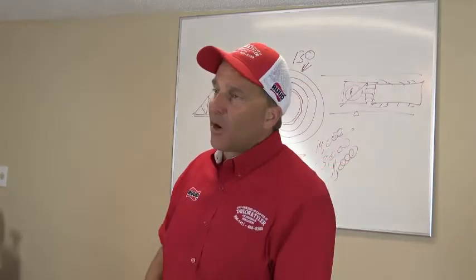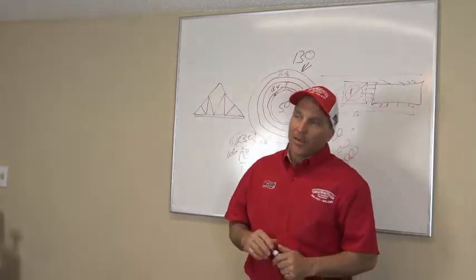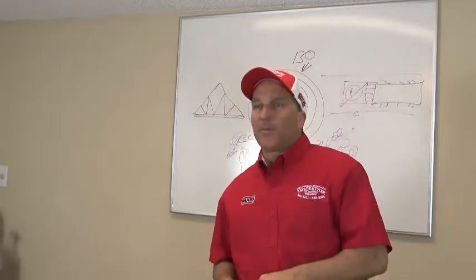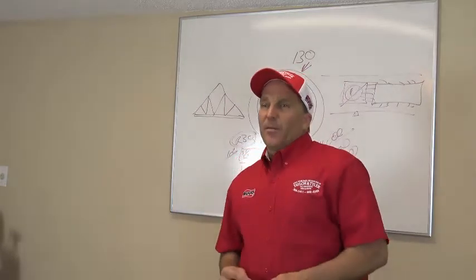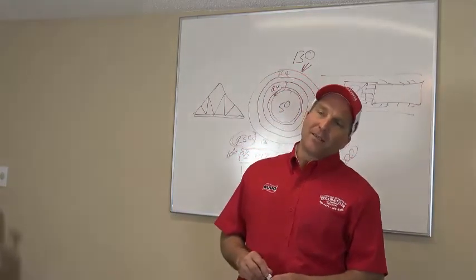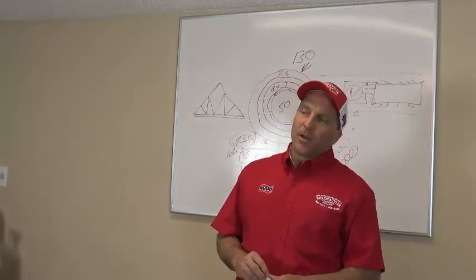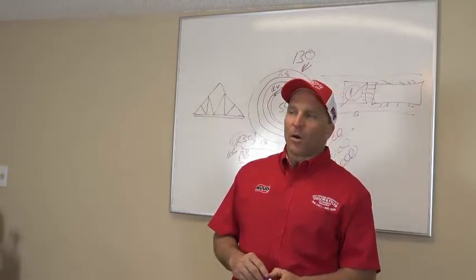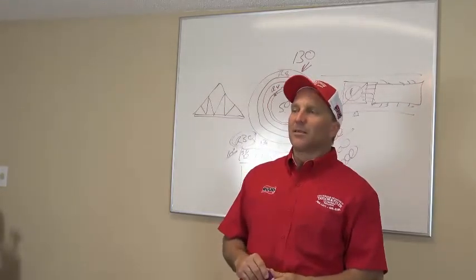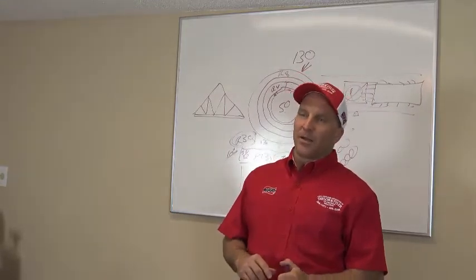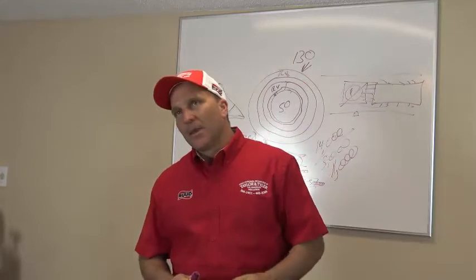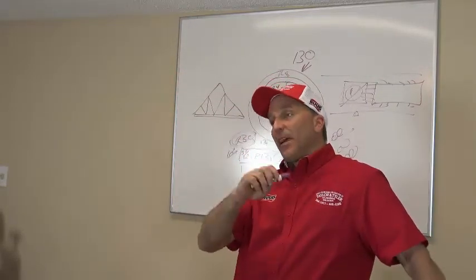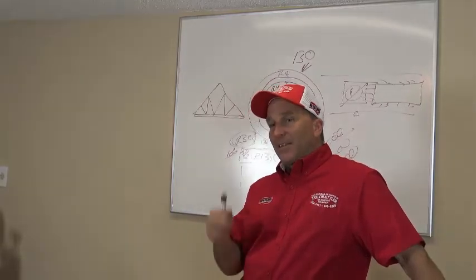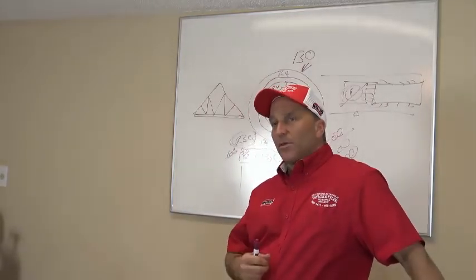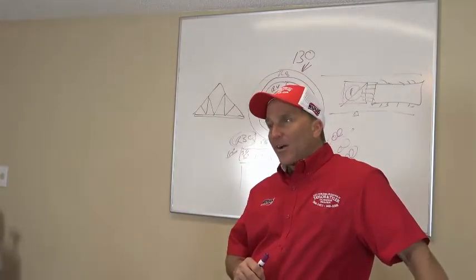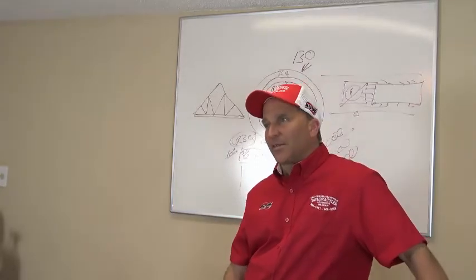I had a guy one time call me up, dude, 9 o'clock at night. This is a true story. 9 o'clock, 9:30 at night, called me up. I was working on one of my rental properties, and he says, this is probably 10 years ago, man. He says, your guy screwed my system up and it don't work. He just put a new compressor in, and it don't work. And he did this, and he did that, and I'm suing you. And I said, I tell you what, I think he put a new condenser fan motor in. That's what he did, okay? And he said, every time I put my fuse in, it blows a fuse. I told him, well, he probably got a bad compressor. Well, your guy caused it because it wasn't doing that before he came out here yesterday.